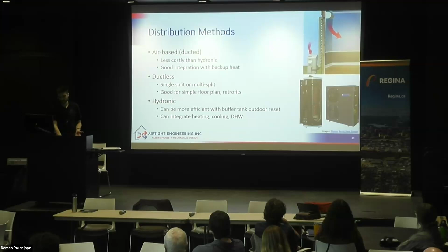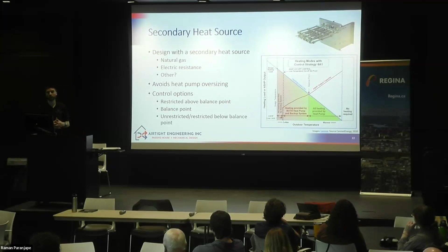I'll touch on this: in Saskatchewan, cold climate heat pumps work, but we do need backup heat - either natural gas, electric resistance, or something else as our backup heat source. It's also important to avoid oversizing a heat pump, because often we're cooling with it as well. We want to make sure we don't oversize for heating and then end up with an oversized cooling system. That's an important design consideration.